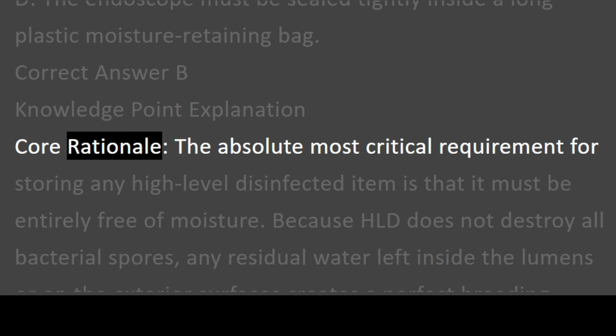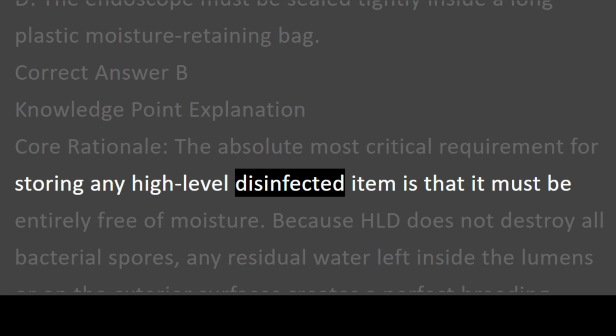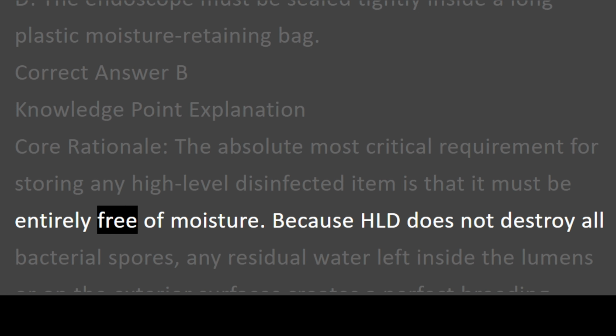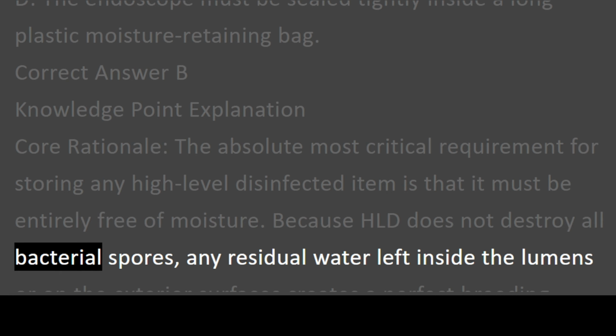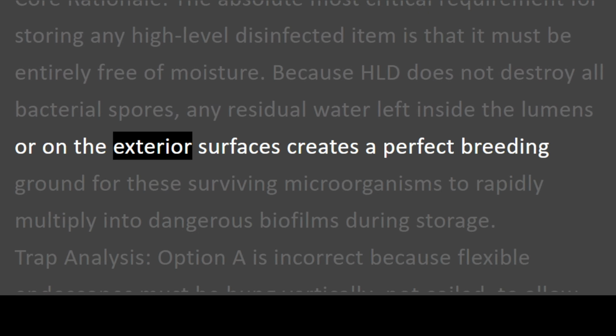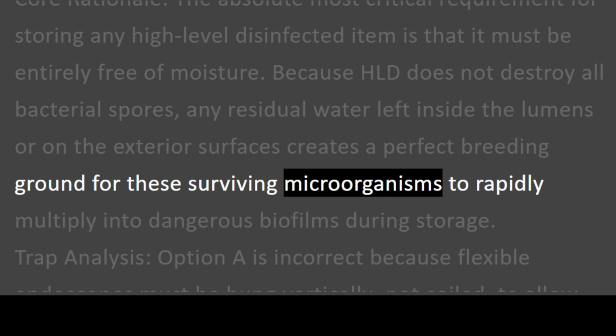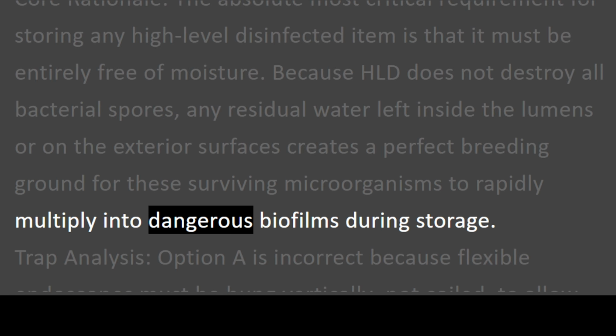Core rationale. The absolute most critical requirement for storing any high-level disinfected item is that it must be entirely free of moisture. Because HLD does not destroy all bacterial spores, any residual water left inside the lumens or on the exterior surfaces creates a perfect breeding ground for these surviving microorganisms to rapidly multiply into dangerous biofilms during storage.